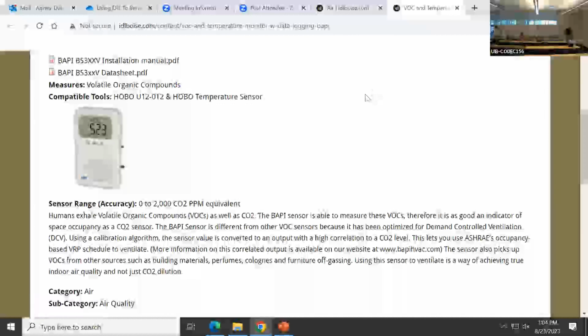So it's not the most detailed, but it can pick up things that CO2 monitors don't - off-gassing paint is one example. We measured it in a building and it was just off the charts for VOC, but it was in an unoccupied space and CO2 was dormant, yet people were complaining about fumes. We found out paint was involved - there was renovation happening a few floors down, and it was going up to the chase and getting sucked in there.